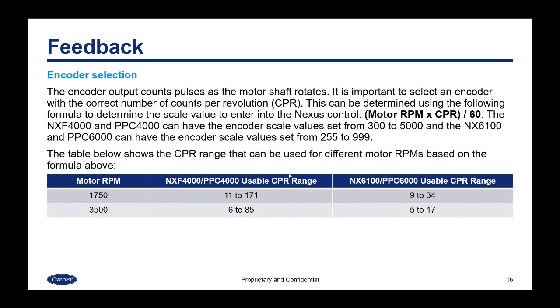The encoder works by counting pulses as the motor shaft rotates. It is important to select an encoder with the correct number of counts per revolution. The scale value is determined by the formula: motor RPM × counts per revolution divided by 60. The NXF4000/PPC4000 accept encoder scale values from 300 to 5000; the NX6100/PPC6000 accept 255 to 999. For example, with a 1750 RPM motor, usable counts per revolution for the 4000 range from 11 to 171, and for the 6100/6000, from 9 to 34.